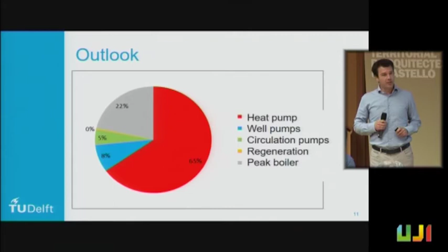That's where this triplet system comes in, where we don't use the heat pump anymore. We want to get all the heat we need from the solar panels, put that in a very warm well that we can use to provide heating in winter. In winter we can get extra cooling capacity from dry coolers, for instance, to get the cooling capacity we need in summer. You need this intermediate well to prevent polluting your warm and cold wells when you're not able to produce the right temperatures at various times during the year.